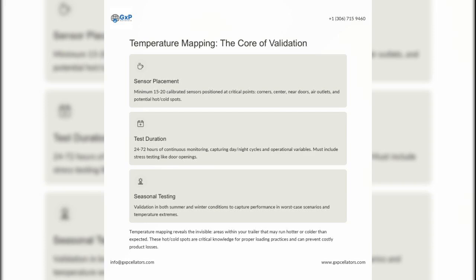Temperature mapping is the core of validation, involving sensor placement, test duration, and seasonal testing. Sensors are placed at critical points to capture day, night cycles and operational variables, including stress testing. Seasonal testing in both summer and winter conditions ensures performance in worst-case scenarios and temperature extremes. Temperature mapping reveals the invisible areas within your trailer that may run hotter or colder than expected. These hot, cold spots are critical knowledge for proper loading practices and can prevent costly product losses.